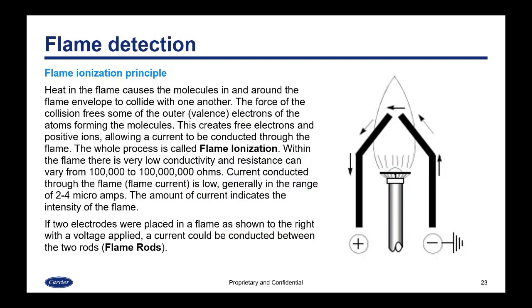Now we're into the methods of flame detection. First, we have the flame ionization principle. Heat in the flame causes the molecules in and around the flame envelope to collide with one another. The force of the collision frees some of the outer or valence electrons of the atoms forming the molecules in the flame. This creates free electrons and positive ions, which allows a current to be conducted through the flame — the whole process is called flame ionization. Within the flame there is very low conductivity and resistance can vary from 100,000 to 100 million ohms. Therefore current conducted through the flame is very low, typically in the range of two to four microamps. The amount of current indicates the intensity of the flame.